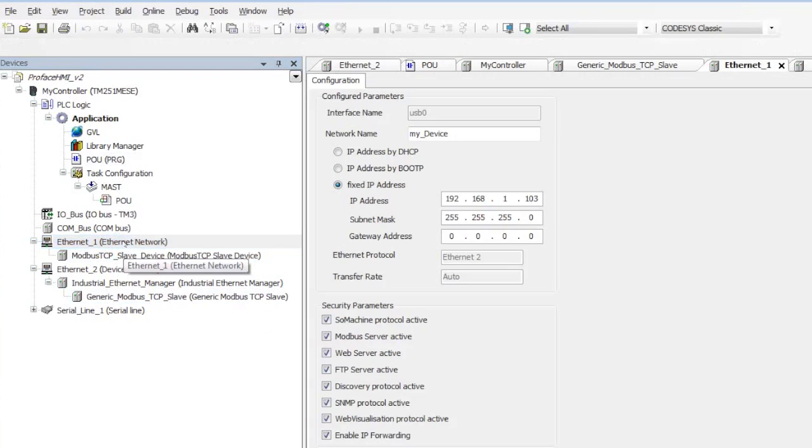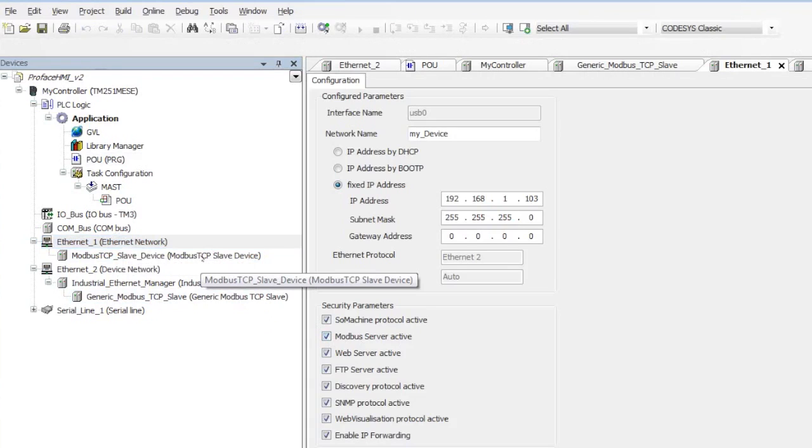If I click on Ethernet 1, you can see the Modbus server is active. However, when you add a slave device here, it overrides that. You're not going to have access to the same registers. Basically, it's one or the other.